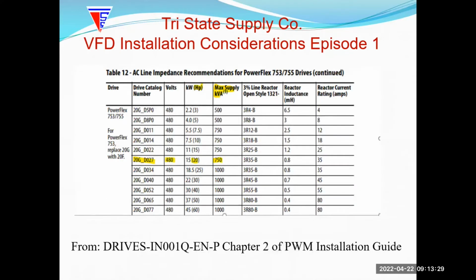We're going to be concentrating on these episodes on the 750 drive family, but the PWM installation guide covers the various drives Allen Bradley offers. And they'll continue to update that as they release new drives. So if we look at the 750 chart, 480 volt in the PWM guide, we go to a 20 horsepower drive here. We look, it's 750 kVA maximum size that we want before we definitely recommend adding an input reactance in front of the drive. Now that could be a reactor, could be adding another drive isolation transformer, or if you had a harmonic filter, it has a built-in reactor as well.